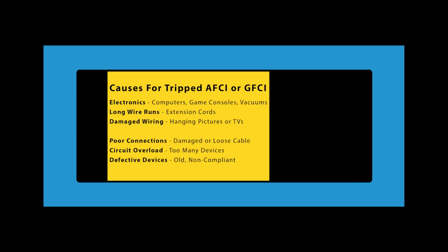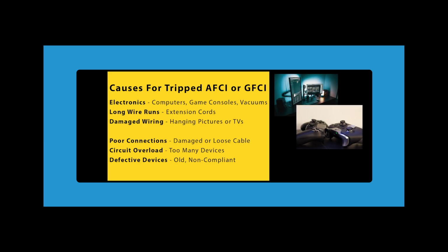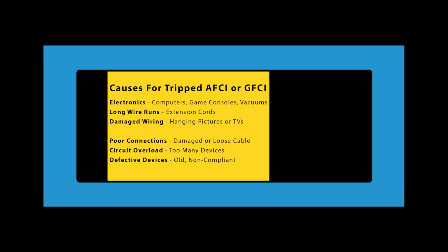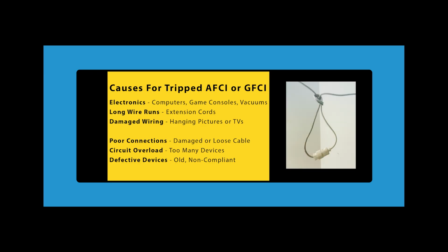So what type of situations can cause AFCI protection to kick in? First on the list are electronic devices. Many modern electronic devices like computers, gaming consoles, and even vacuum cleaners can generate electrical noise that AFCI breakers may misinterpret as a dangerous electrical fault. Second, long wire runs might be the culprit. As wires get longer, they're more likely to pick up electrical noise or exhibit increased capacitance, which can lead to nuisance tripping. So if you encounter a situation where you always seem to be tripping an AFCI breaker when you're using an extension cord, then the extension cord itself might be the issue.